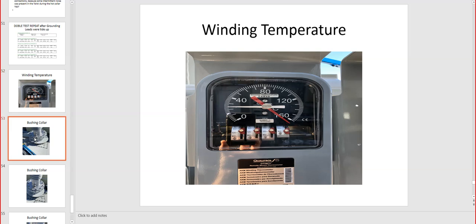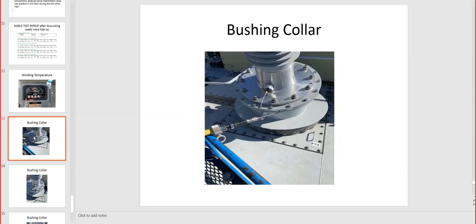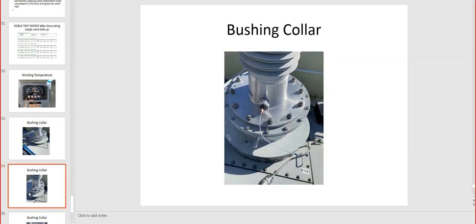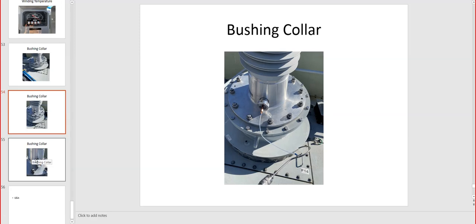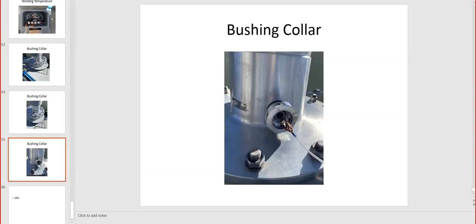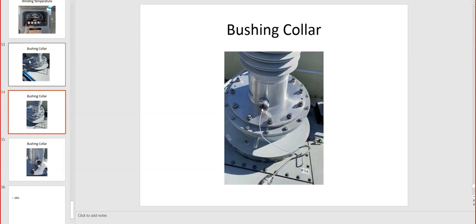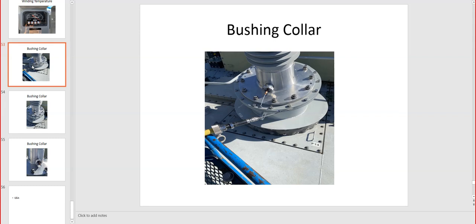And the next two pictures are going to show you how we apply the collar on the tap for the bushing test, applying those voltages and reading the leakage current, the dissipation factor or power factor, and reading the capacitance. This is another one after cleaning, how it was actually applied, the correct test. And the third one, right? So this is the installation of the bushing collar, and that will bring us to the end of the presentation.